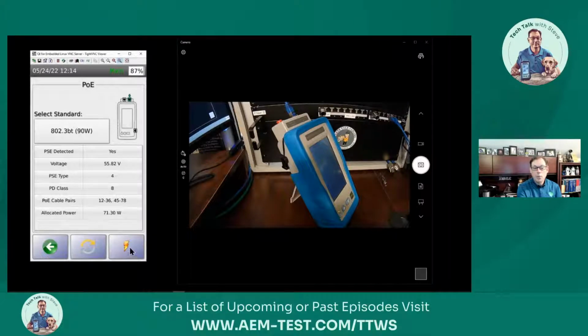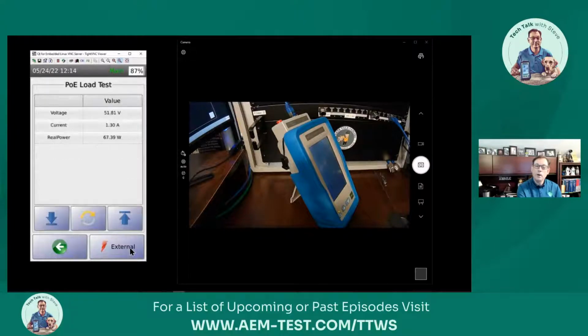So we're going to go ahead and hit this lightning bolt. That's our load test, and we're actually going to demand the load from the switch, just like the NSA was a PoE device. We see here that we're getting 67.39 watts. So that is the power we can actually get at the end point of this cable, not 71.3.